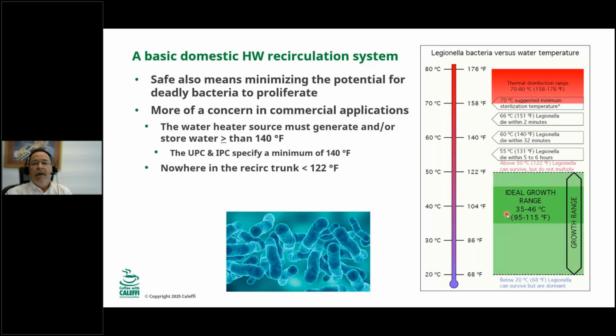So the UPC and IPC codes, for example, specify a minimum of 140 Fahrenheit for your storage temperatures. Why do they do that? Because of this table on the right, right? If you store at 140, you will not have Legionella growth in the tank. And theoretically, then we don't want anywhere in that recirc loop to drop below 122 if you're using this chart here.